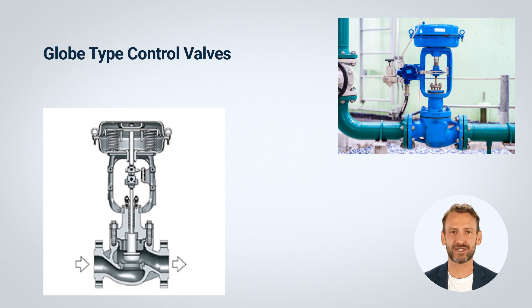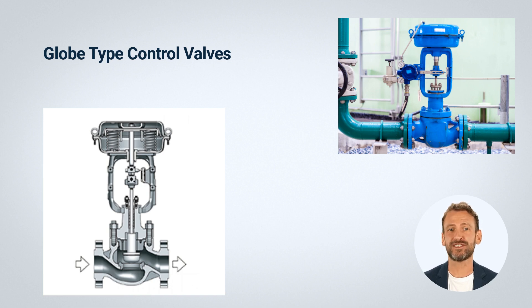Flow characteristics: globe valves typically have a higher pressure drop than other types of valves, which can make them less efficient in some applications. However, they also offer precise control over flow rates, making them ideal for applications that require accurate flow regulation.